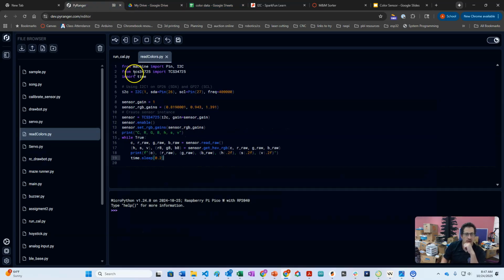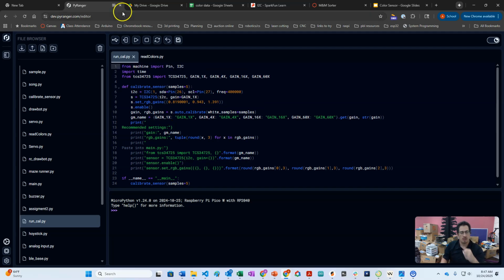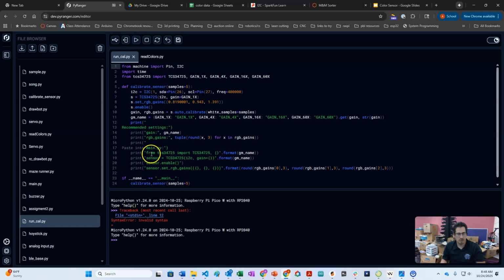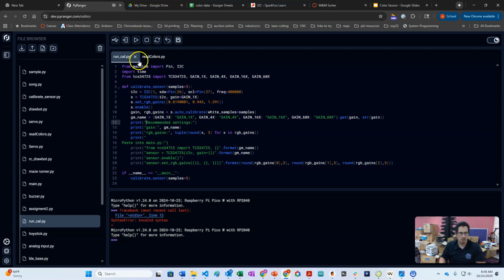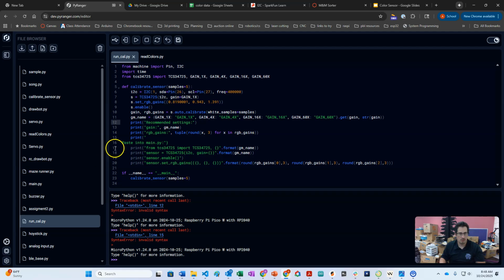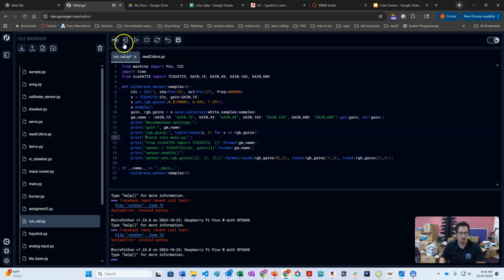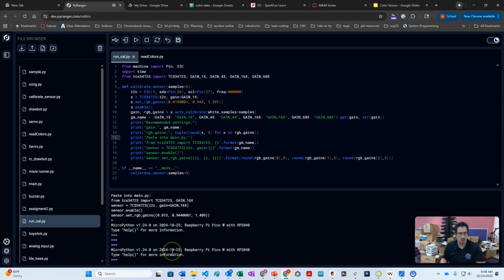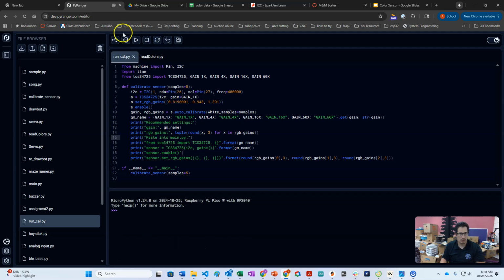So I'm using this random plastic thing that I found, and the way that we do it is we've got this run cal script, and basically you're going to hold that thing over the sensor and you're going to click this, and this is going to, oops, didn't like that, line 12, this thing got broken, there we go, line 15, this got broken too, I wonder what happened there, okay. Okay, so I'm going to run it, and it's done this gain calibration for me.